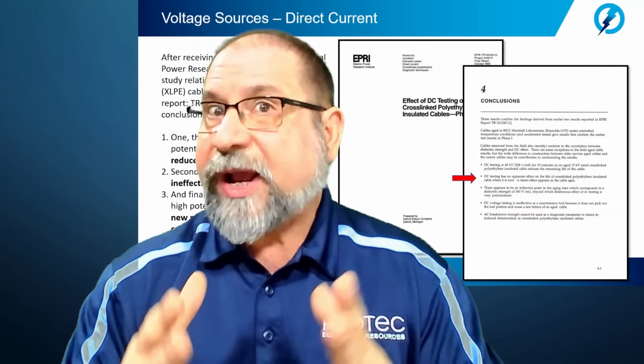Okay, the EPRI report also provided the following recommendations. To be safe, it is recommended not to conduct any DC testing at 40 kV, or corresponding to a stress of 228 volt per mil, on crosslink polyethylene insulated cables in service. DC testing can be done up to 55 kV in the field on an unaged cable, basically a cable that has never been in service.